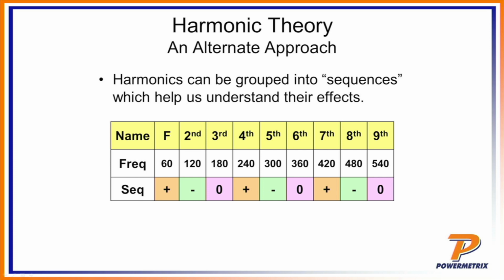Let's talk about an alternative approach to look at harmonic theory. Harmonics can be grouped into sequences, which helps us to understand their effects. So once again, if we talk about each of the harmonics, we have the fundamental at 60 hertz, second at 120, third at 180, and so on and so forth. If we look at sequencing, we have positive, negative, and 0th order harmonics. The positive happens on every fourth, so you go fundamental, fourth, seventh, etc. Negative happens second, fifth, eighth, and then on the thirds we're going to have 0.